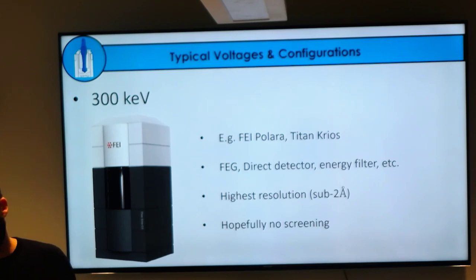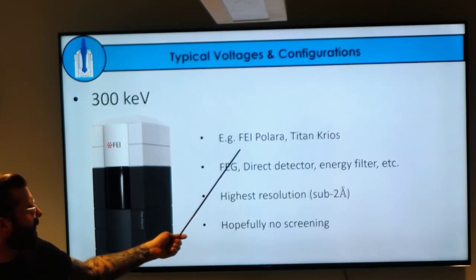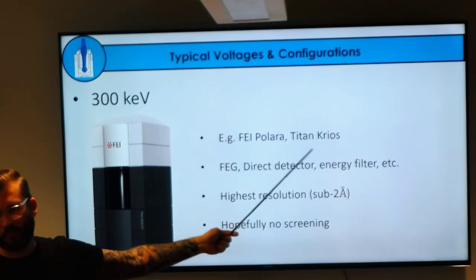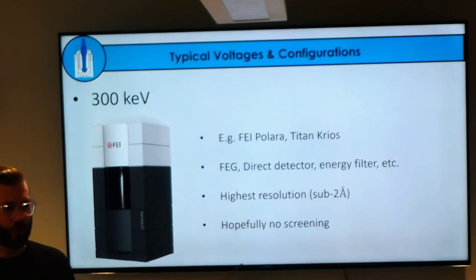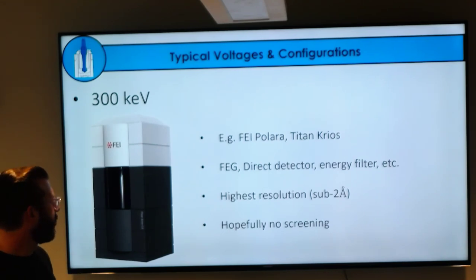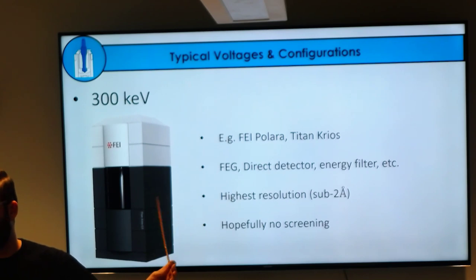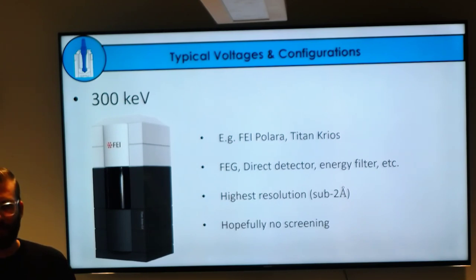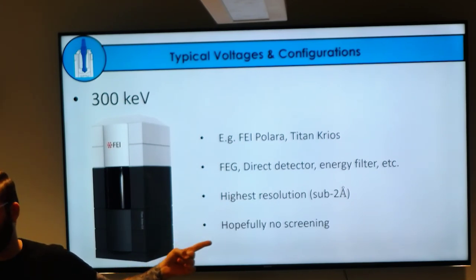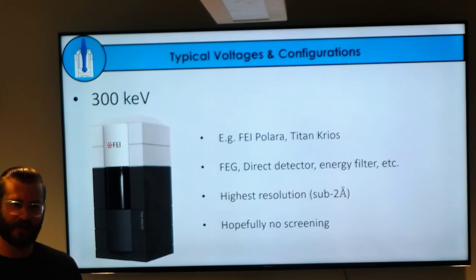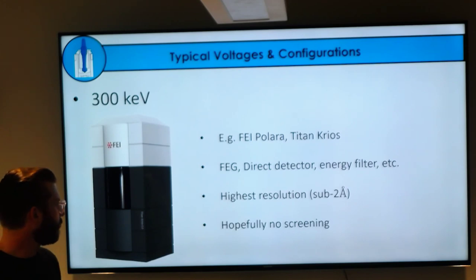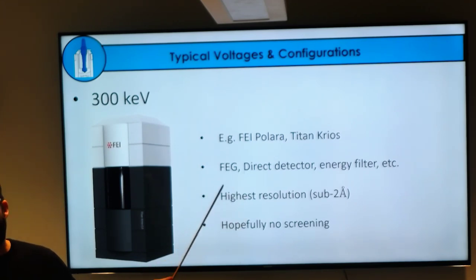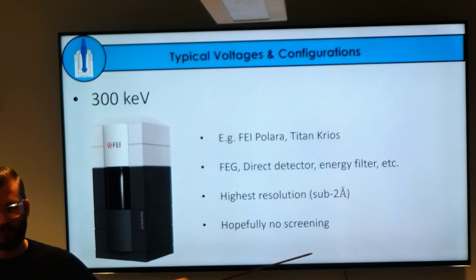At the very high end, the one everybody wants to use, is 300 kV. You have somewhat older models like the FEI Polara, or most famously the Titan Krios or the Jeol Cryo-ARM. These are equipped with top-of-the-line stuff: field emission guns, direct detectors, energy filters, phase plates, CS correctors, and other things that improve imaging. These are capable of the highest resolution sub-2-angstrom range; I think apoferritin at 1.5 angstroms is currently the highest.